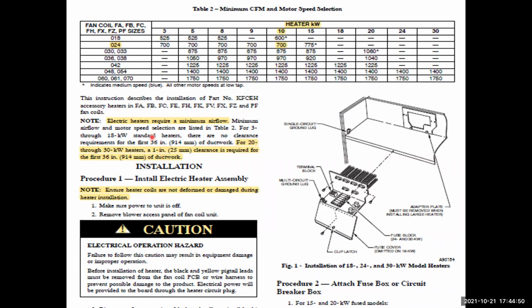Okay, notes that they talk about on the heaters. It says 20 through 30-kW, the larger heaters, you have to have a 1-inch clearance for the first 36 inches of ductwork. Then there's also a notice right here, kind of give you some caution and tells you what's going on, is notice that the caution to move the wiring pigtail to prevent possible damage. So they're letting you know of that. And then over here, I did not highlight it, but remember to remove the adapter when using the larger, I think it's 28 to 30 kW heaters. So you'll go ahead and remove the first little panel when you're adding your heater in it. On the larger ones, you remove this adapter as well.